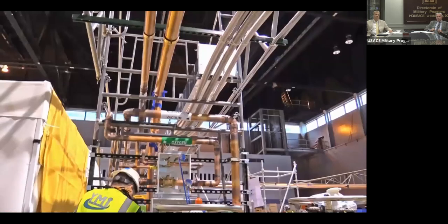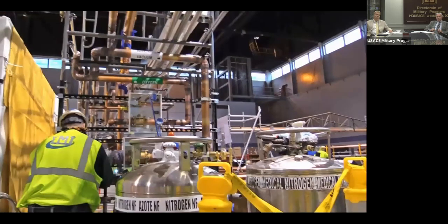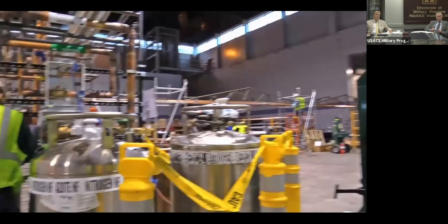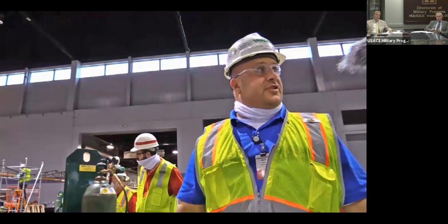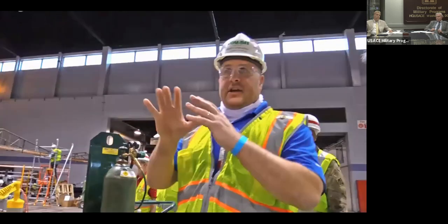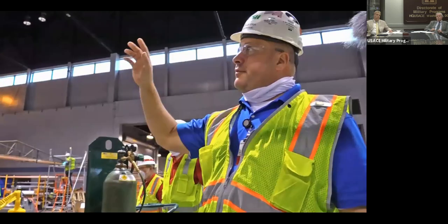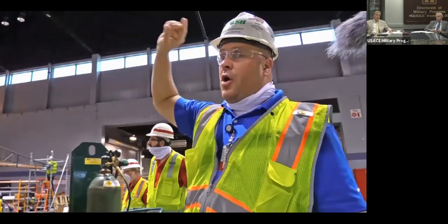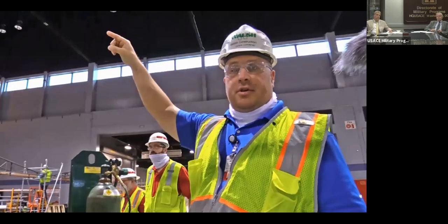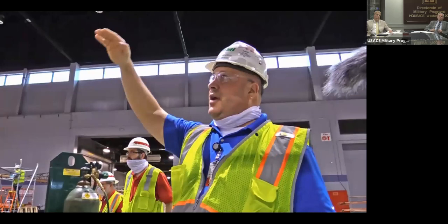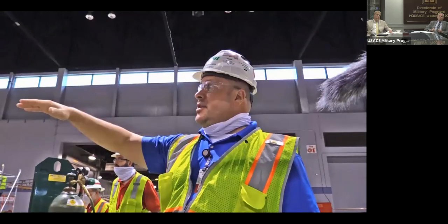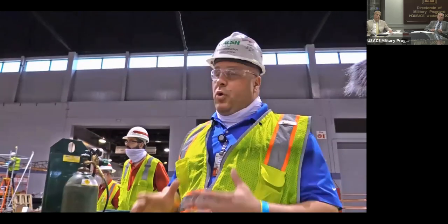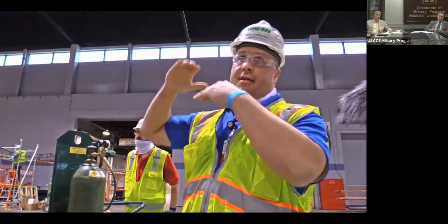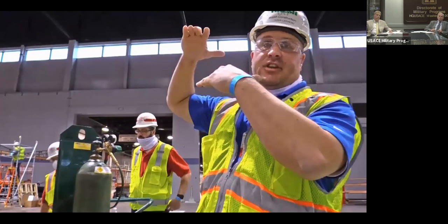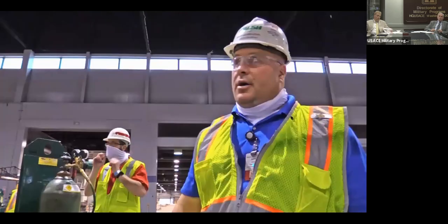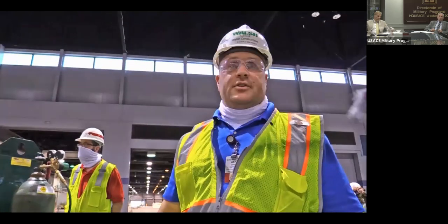So we went through behind all these tents, and you see all this scaffolding system that we typically use for construction. It's behind all the tents, and that's our main thoroughfare. The top part is the ductwork, all the exhaust ductwork that comes out of the tents. Then we see all our oxygen and vacuum running, and the electrical below it. So it worked out great for a racking system. Everybody's given a designated space, and that's how they delivered all the equipment, the power, and all the feeds to each one of these tents that we're using for isolation.